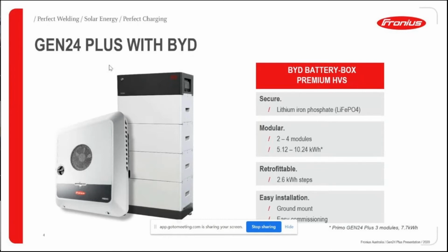In this model here, you can see it's the HVS model, where the S stands for small, because you can stack up to 4 of the modules, which will get you up to about 10 kilowatt hours of storage, going up in 2.6 kilowatt hour steps. Then you've got the HVM model, where you can stack up to 8 modules high, getting you up to 22 kilowatt hours of storage.